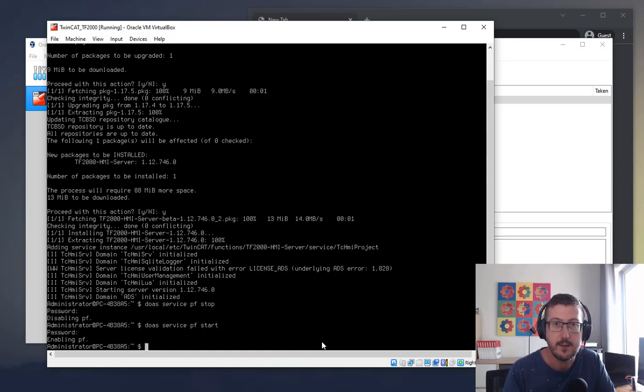It would actually give you a warning as well. If we restarted the virtual PC now, as that auto run kicks in, it says, hey, I'm potentially going to auto run the TwinCAT HMI server. I'll check to see if this variable is set, and it says I can't even find the variable. You'll get a little warning come up saying that the variable's not been set. You'll see it as TC HMI SRV underscore enable, and it'll say it's not been set. So we need to work out where to put that, and we need to set this ourselves. So we've got another command coming up. We're going to doas.